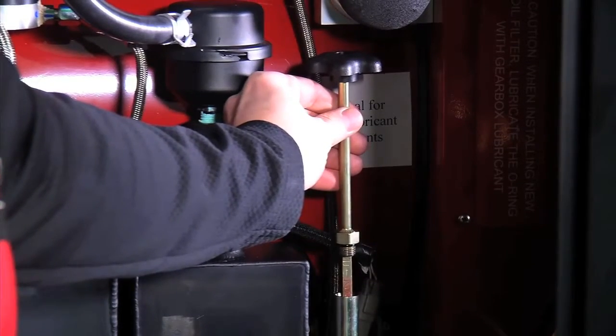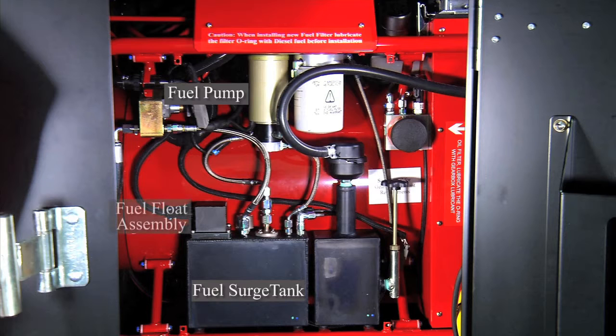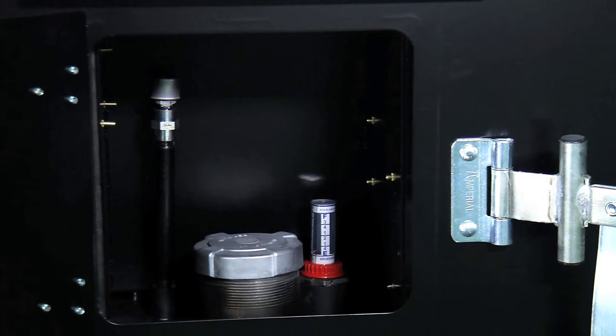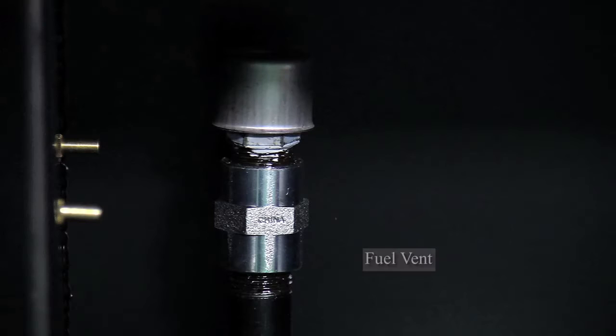It is recommended to change the oil every 3,000 hours and the filters every 1,000 hours or seasonally. This side of the unit also contains the JetHeat fuel pump, fuel surge tank, fuel float assemblies, and oil vapor separator. This side of the trailer has another access door for the fuel, housing the 4-inch fuel filler, fuel height gauge, and fuel vent.